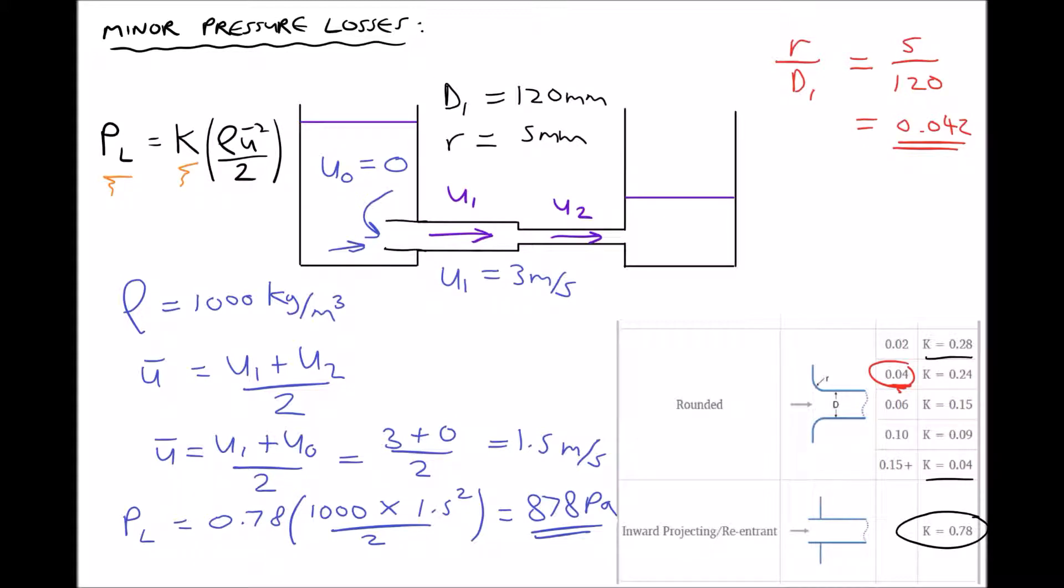So returning to our pressure loss formula, we have pressure loss equals K, 0.24, times ρ ū bar squared over 2. Well we've already said ρ is a thousand, our value of average velocity is unchanged so it's still 1.5 squared over 2, giving us a pressure loss this time equal to 270 pascals. So once again we have a relatively small pressure loss.